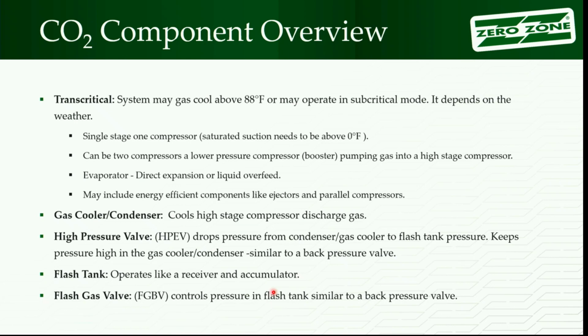A booster compressor takes the gas from the low temperature evaporators, pumps it up, raises its pressure to the pressure of the suction of the high stage compressors. So it moves that gas. If you've done ammonia work, almost all ammonia systems have boosters because they're running at relatively low enough pressure that they can save some energy and avoid high discharge temperatures with a booster. So they exist in the world of industrial for sure. I think there are also some older R22 compound systems floating around out there that, maybe 20 years ago, had some boosters in them as well.